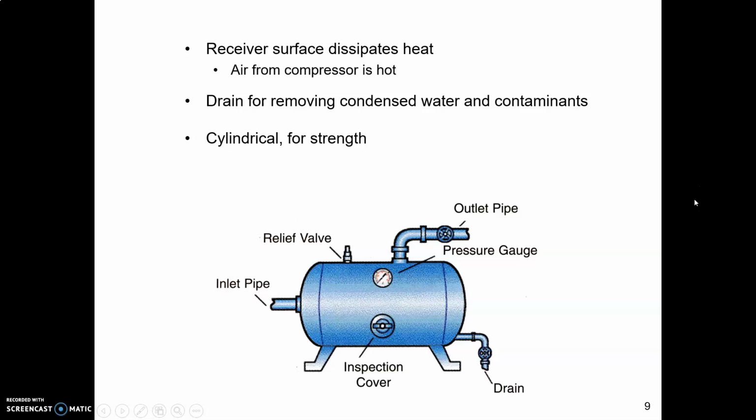The thing about a compressor is when it compresses, the air gets hot. And you can picture those molecules jumping around together as they get compressed. They jump harder and harder, and there's friction between those molecules. That makes the air hot. So it comes into the receiver, and just the surface of the tank dissipates the heat. Then condensation, moisture builds up in that air real easily.